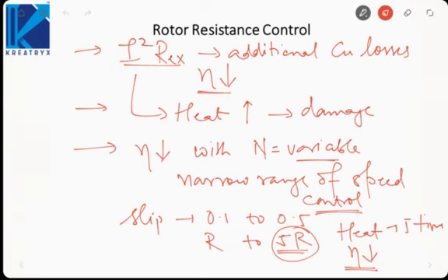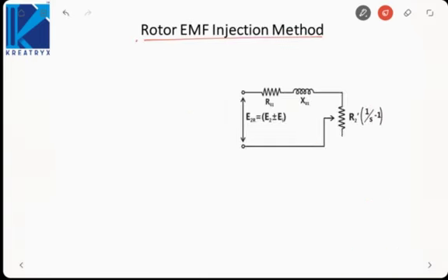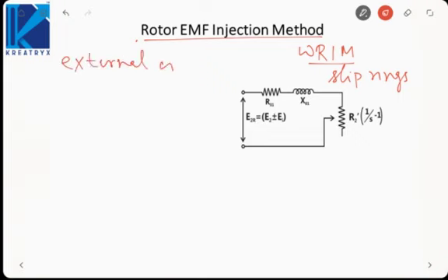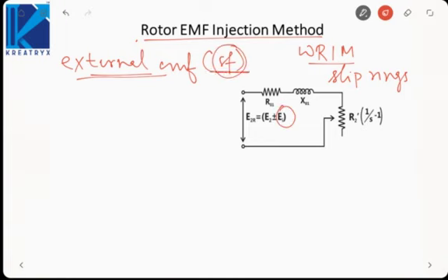The next method is rotor EMF injection, applicable only to wound rotor induction motors via slip rings. An external EMF source with frequency sf is connected — this frequency is required because the injected EMF must match the frequency of the induced rotor EMF to be superimposed on it. The injected EMF can be in the same phase or opposite phase to the induced EMF.